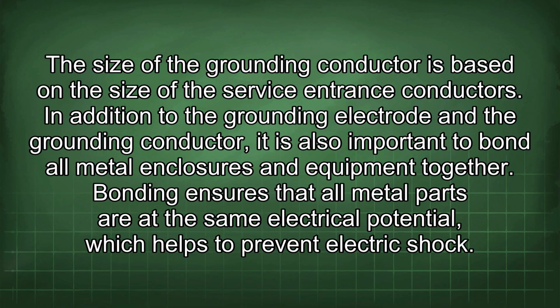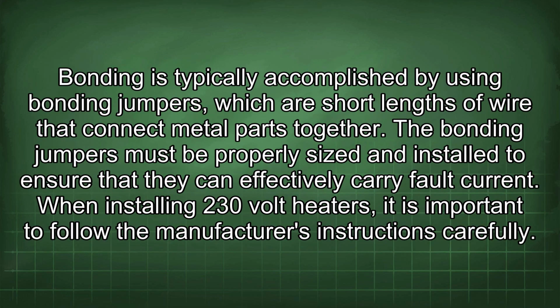In addition to the grounding electrode and the grounding conductor, it is also important to bond all metal enclosures and equipment together. Bonding ensures that all metal parts are at the same electrical potential, which helps to prevent electric shock. Bonding is typically accomplished by using bonding jumpers, which are short lengths of wire that connect metal parts together. The bonding jumpers must be properly sized and installed to ensure that they can effectively carry fault current.